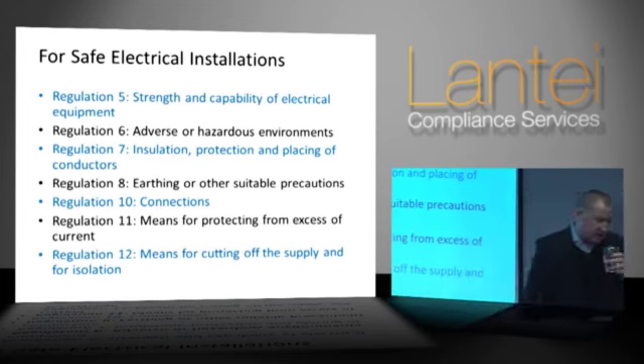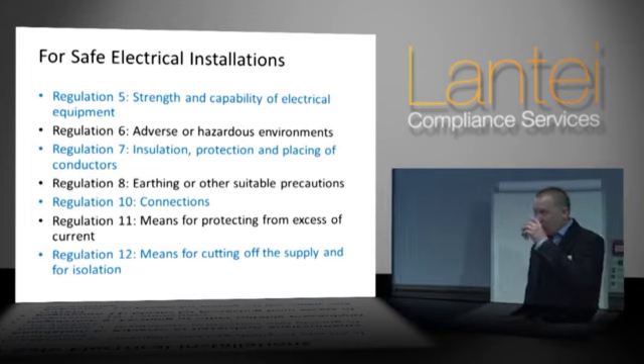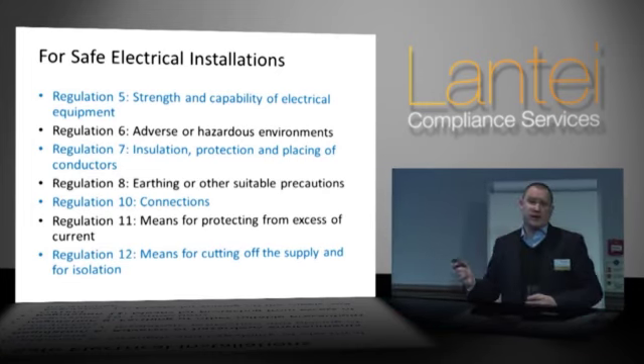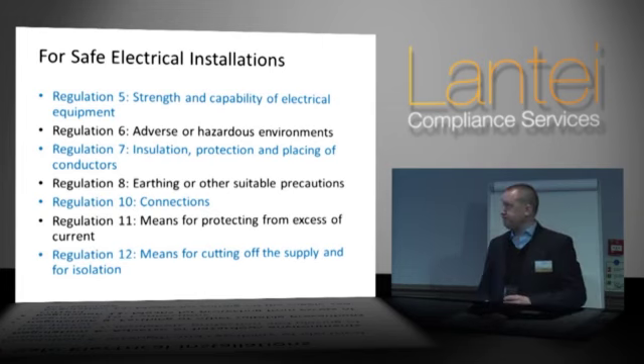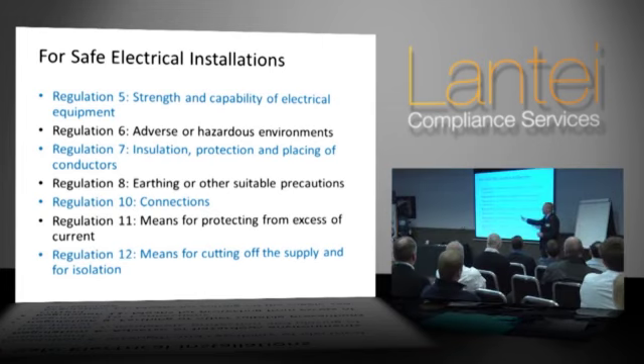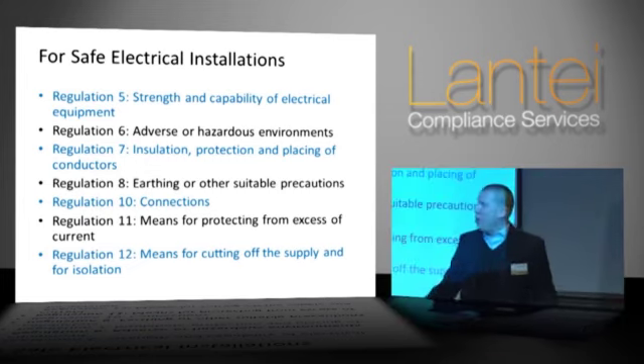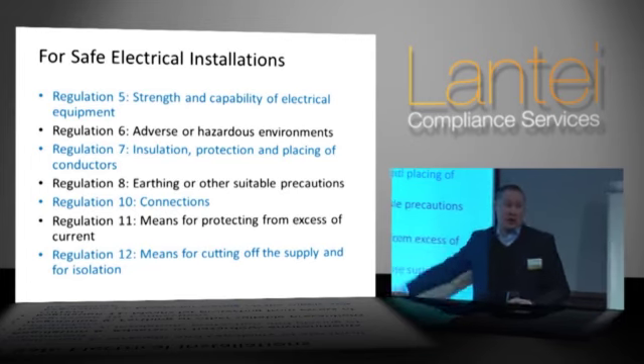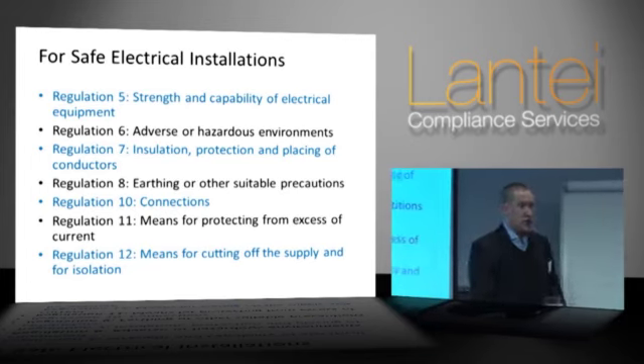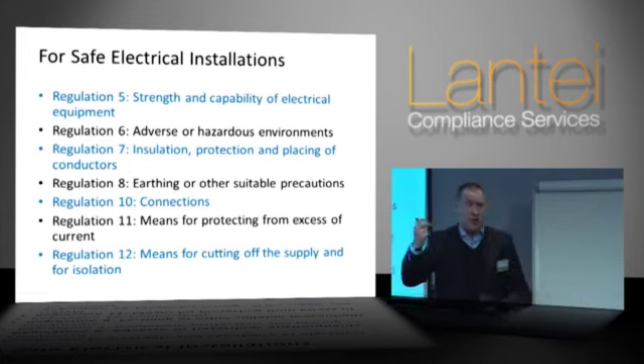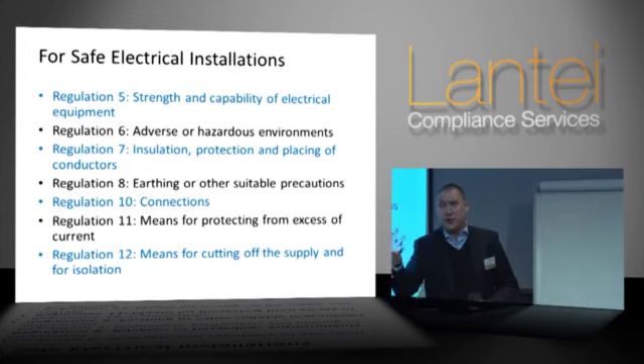So the first one there, Regulation 5, talks about the strength and capability of electrical equipment. Basically what Regulation 5 wants us to do is identify any piece of equipment, doesn't matter what it is — a bit of cable, a switch, a light fitting, a distribution board, an isolator, anything. That regulation wants us to look at that piece of equipment and make sure it's capable of coping with the voltages, the operating currents, and the prospective fault currents that are likely to go through it.